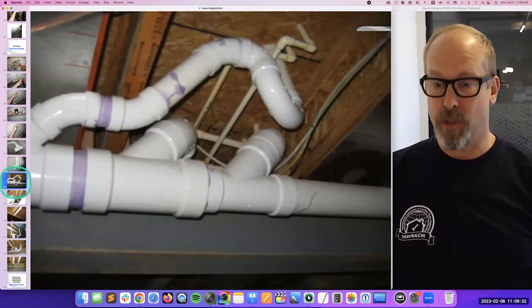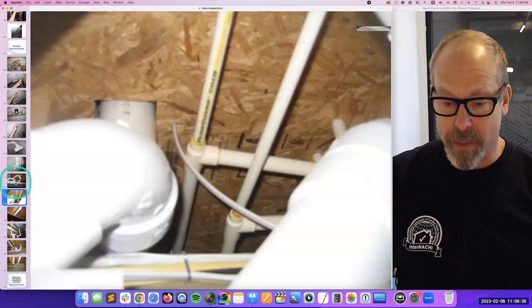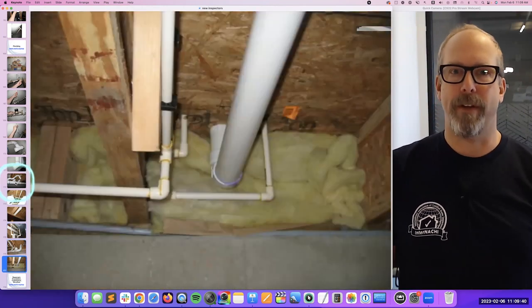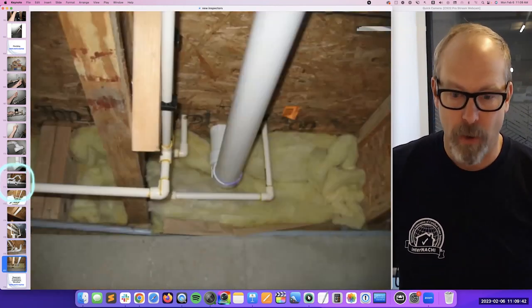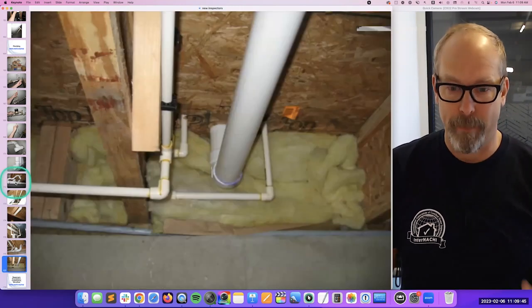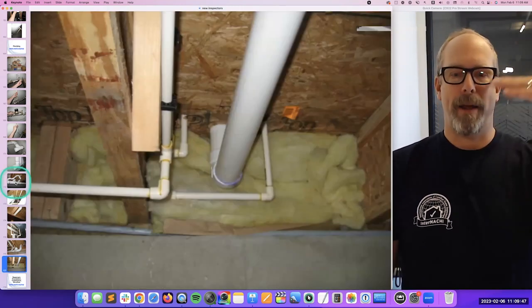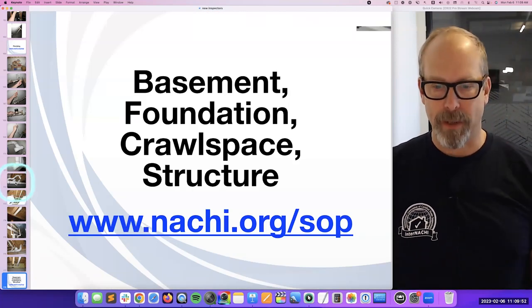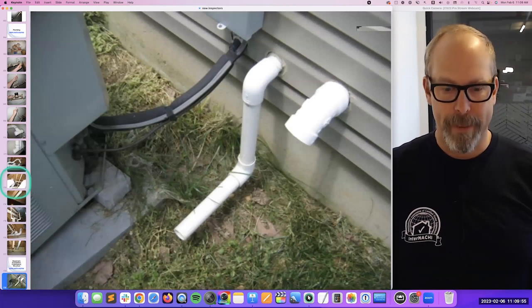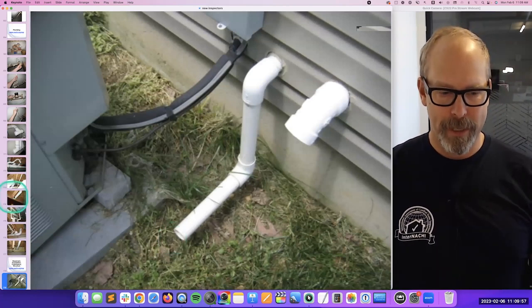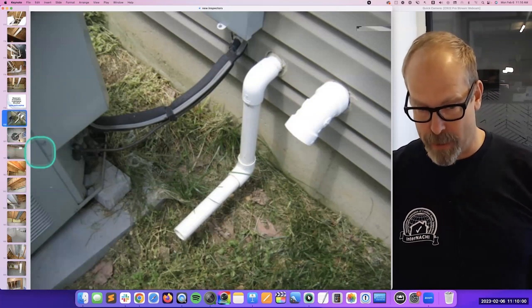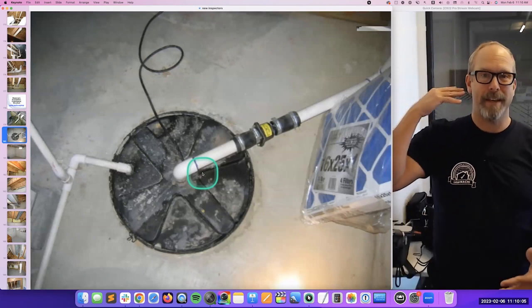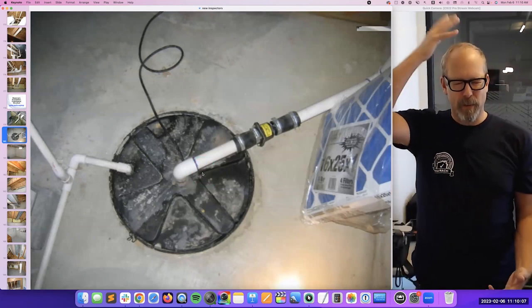To the left here, there's another system. There's public water coming in and I can see the sewer line on the left coming out. I'm touching from where the water comes through the foundation wall, through the shutoff ball valve. There's another shutoff valve on the other side, a water meter in between, a jumper cable, and bonding. There's sewer going out — water coming in, sewer going out. There are clean-outs and sewer pipes. And there are the water supply pipes — they're plastic, that's okay. I'm just looking for anything that's leaking. I'm required to inspect all this: basement, foundation, crawl space structure.